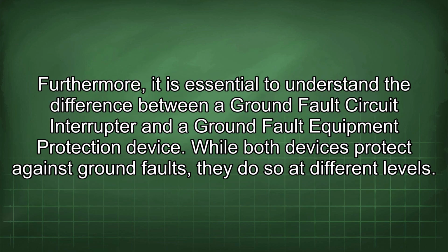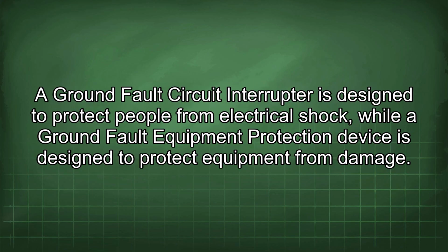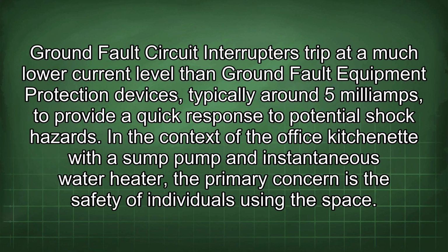Furthermore, it is essential to understand the difference between a ground fault circuit interrupter and a ground fault equipment protection device. While both devices protect against ground faults, they do so at different levels. A ground fault circuit interrupter is designed to protect people from electrical shock, while a ground fault equipment protection device is designed to protect equipment from damage. Ground fault circuit interrupters trip at a much lower current level than ground fault equipment protection devices, typically around 5 mA, to provide a quick response to potential shock hazards. In the context of the office kitchenette with a sump pump and instantaneous water heater, the primary concern is the safety of individuals using the space.